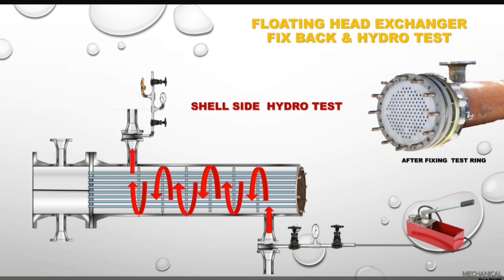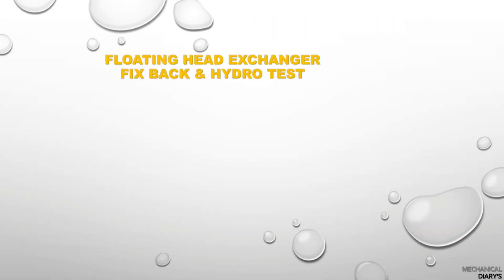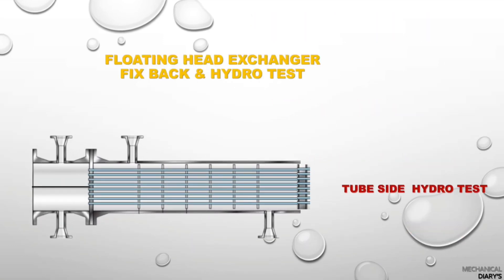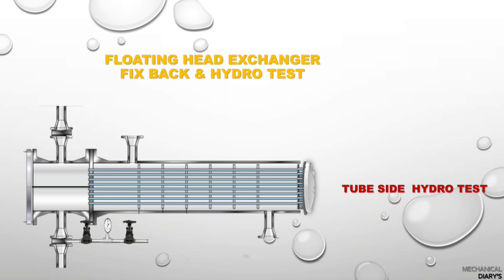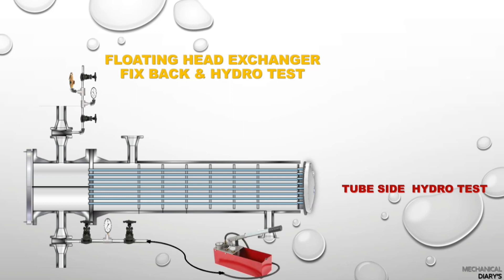Once the test pressure is reached, call the inspection team for clearance. After getting inspection clearance, the next activity is the tube side hydrotest. For tube side hydrotest, first remove the test ring, then fix the floating head in that area, then fix the channel cover. Properly set the gasket and tighten all bolts before pressurizing.